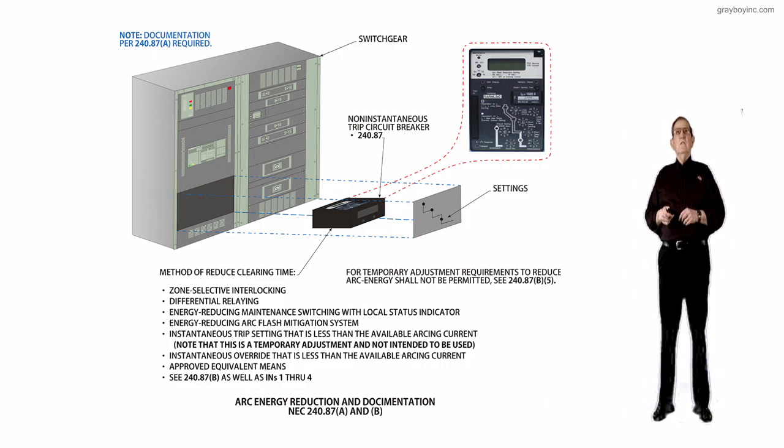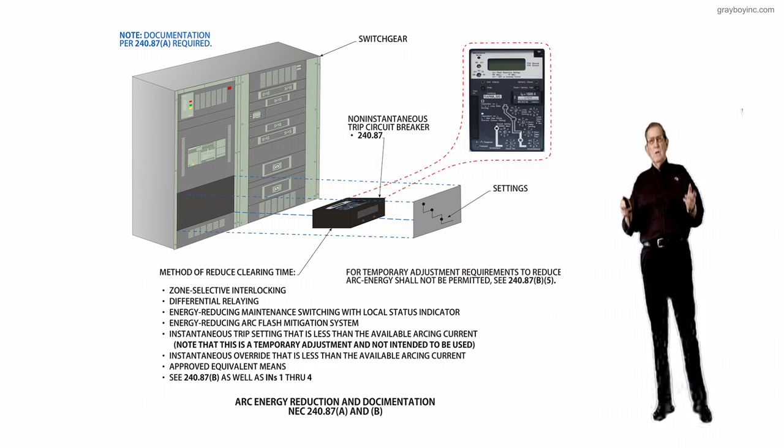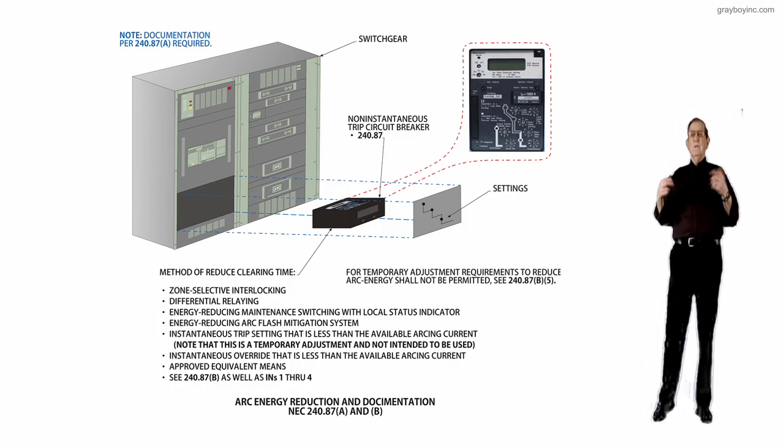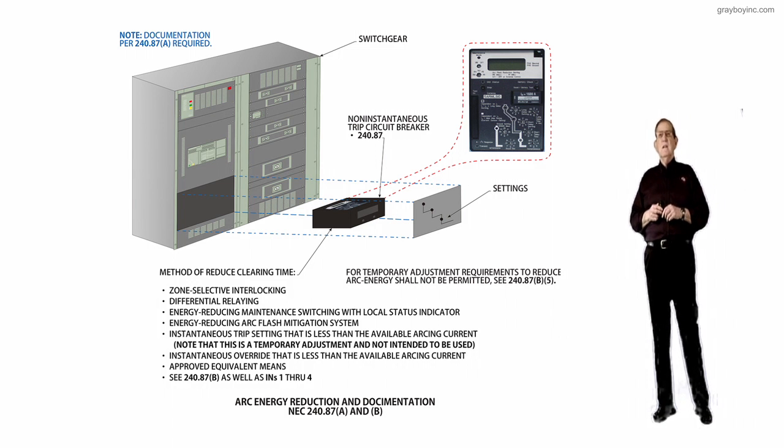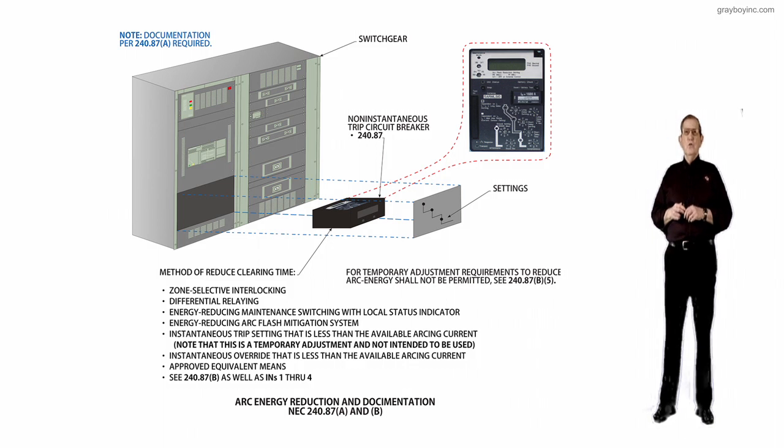And then, of course, the final note up here, right above the switchgear, says documentation for 240.87(A) is required. So we have to have the documentation that it will function in a reliable and dependable manner and present that to the authority having jurisdiction.